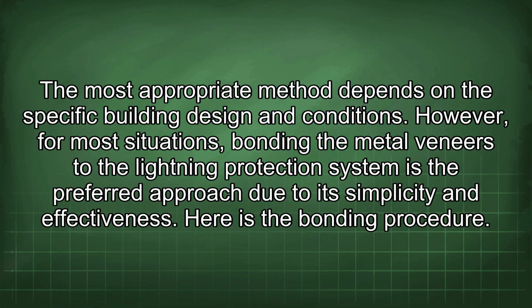The most appropriate method depends on specific building design and conditions. However, for most situations, bonding the metal veneers to the lightning protection system is the preferred approach due to its simplicity and effectiveness. Here is the bonding procedure.